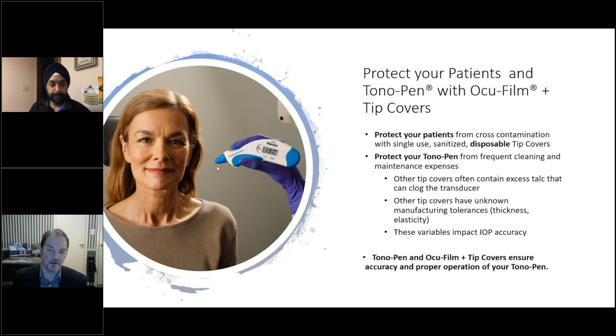They can also affect the lifetime and the maintenance requirements of your Tono-Pen, because latex products like a latex glove, for example, have talc inside of them. We control very carefully the amount of talc that goes in those, so we're not clogging up the tip of the Tono-Pen that's got very small clearances around the transducer. Some of the other manufacturers use too much talc in their tip covers, and it causes you to have to send in your Tono-Pen for cleaning or service on a more frequent basis.